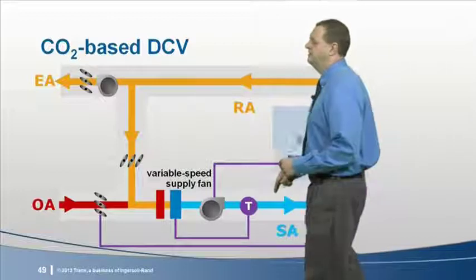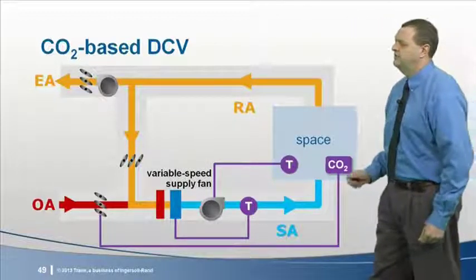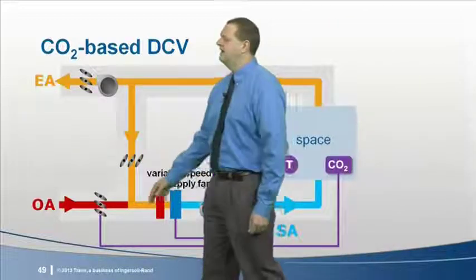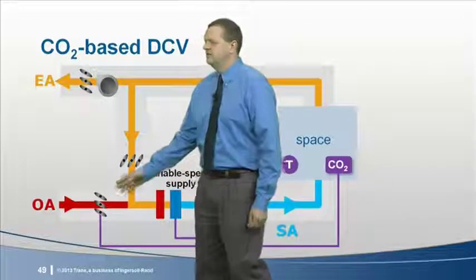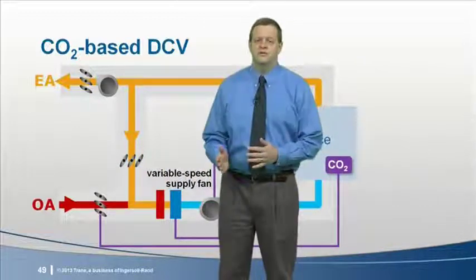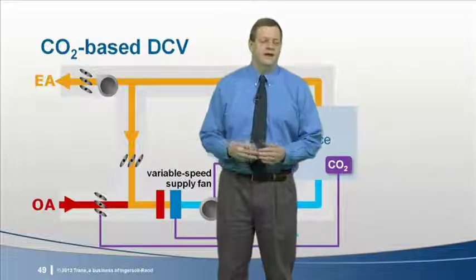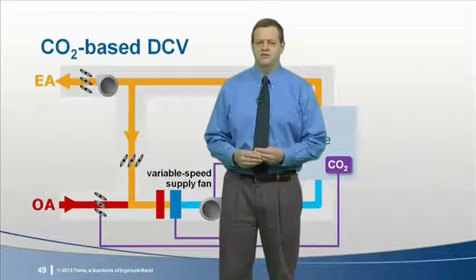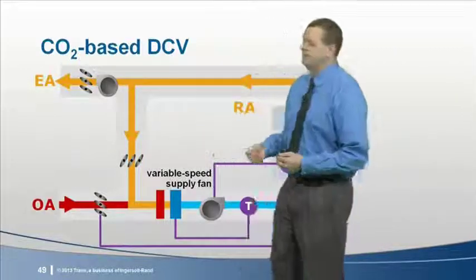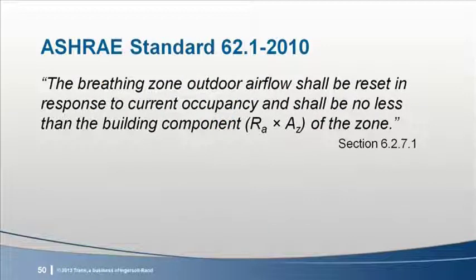With this approach, a sensor measures the concentration of CO2 in the zone. This concentration is used by the controller to reset the outdoor airflow as population changes. This saves energy by not overventilating the zone during periods of partial occupancy. However, while ASHRAE Standard 62 allows the use of demand control ventilation, it also includes a few requirements to make it work. For example, the controls cannot be allowed to reduce outdoor airflow any lower than the building component of the ventilation rate. This is defined by the CFM per square foot rate, or R sub A, that's listed in the standard for that type of zone. So while the CFM per person component can be varied, you cannot go any lower than the CFM per square foot component.